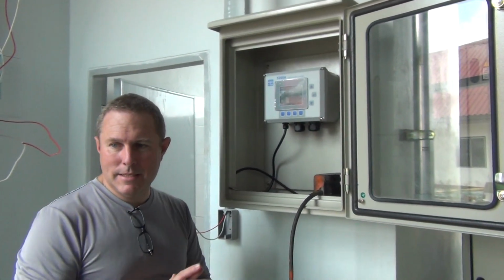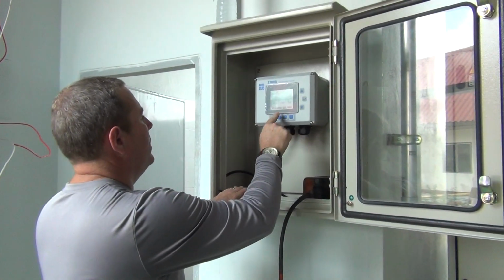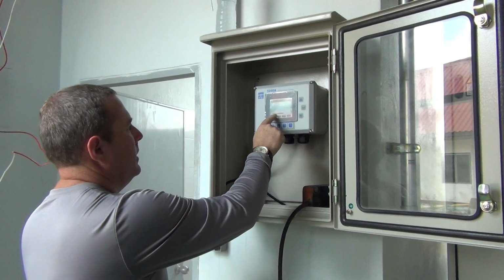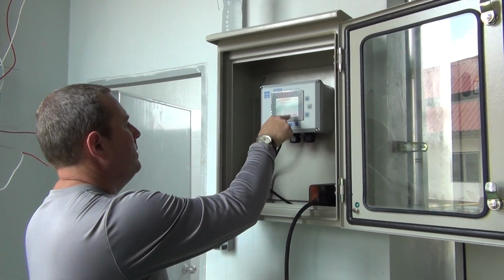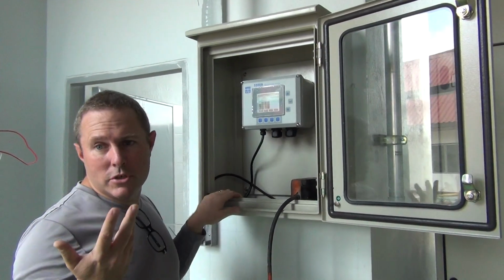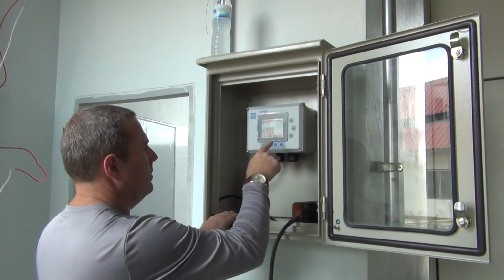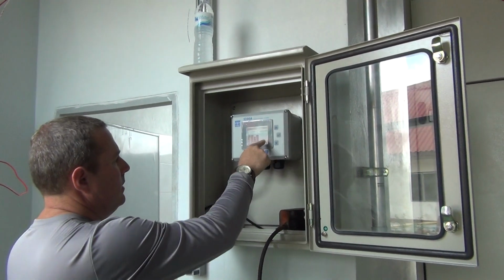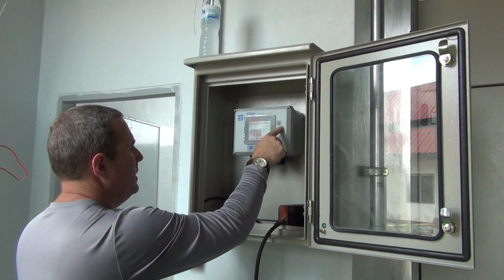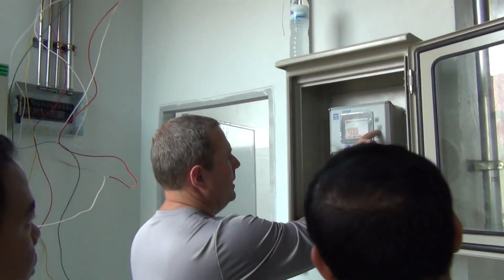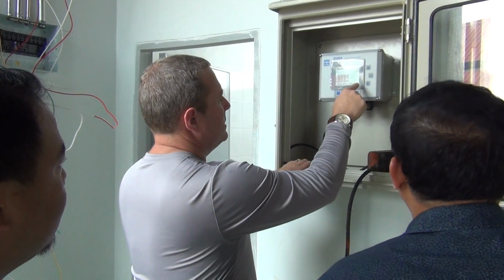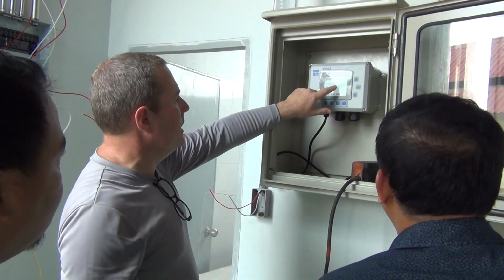You know, the more we've just said this, I think maybe we turn it on for like 15 minutes or 30 minutes. Because if you're calibrating or cleaning the probes, you don't want the pumps turning on and off randomly, right? Yes. So that's where we would use it. Does that make sense now? Yes. So I'm going to go back to menu, system, service hold. I'm going to enable it, and I'm going to set it, 30 minutes should be more than enough. Yeah, 30 minutes would be more than enough. Yes. So I go to the 3, and I'm going to go to the 0, 30, up, I went one too far, up, backspace, and I'm going to press save, and now it says 30 minutes.